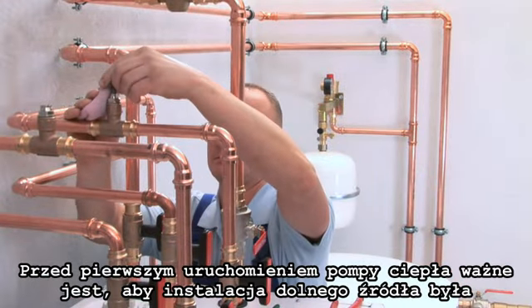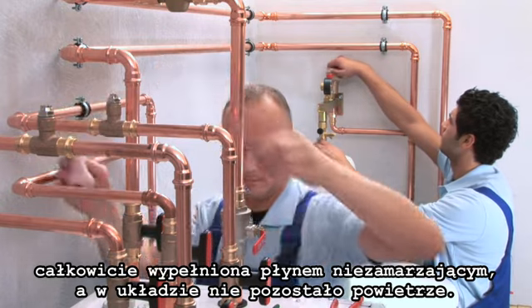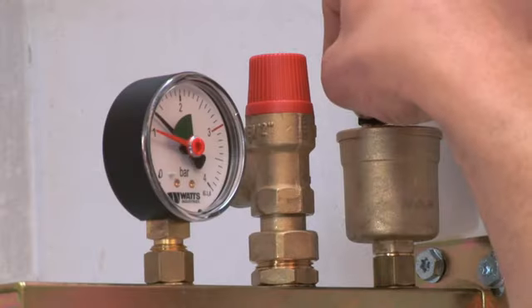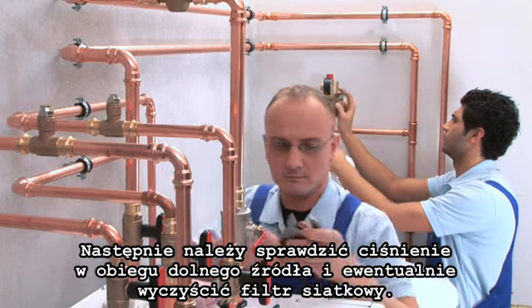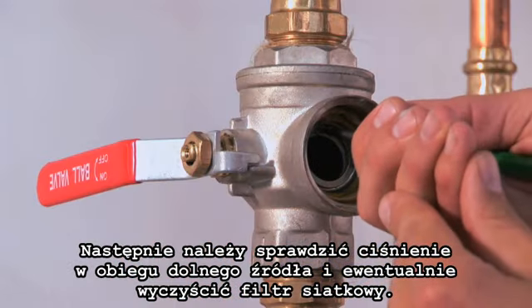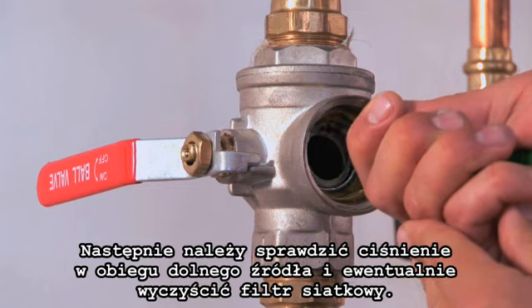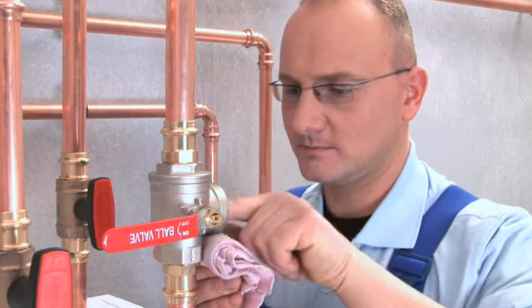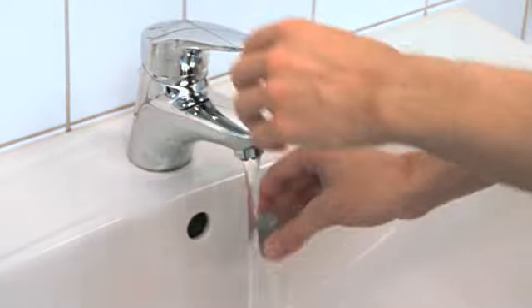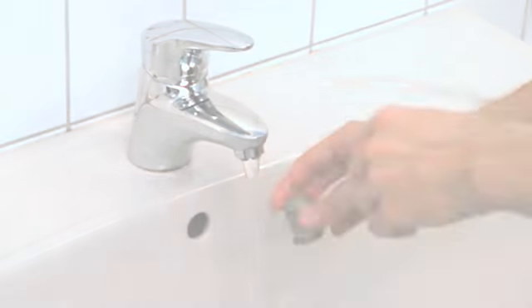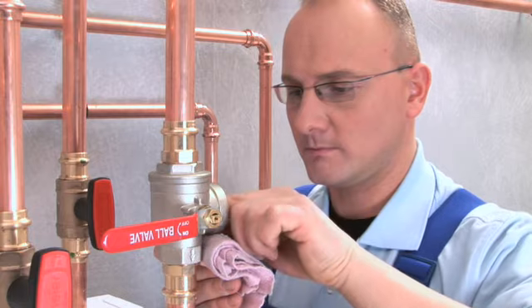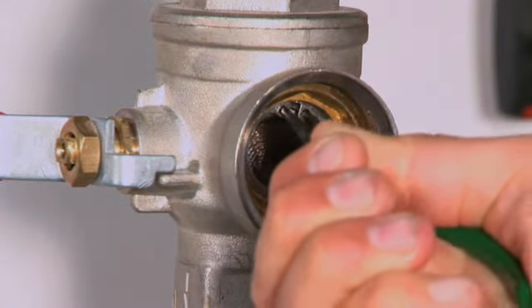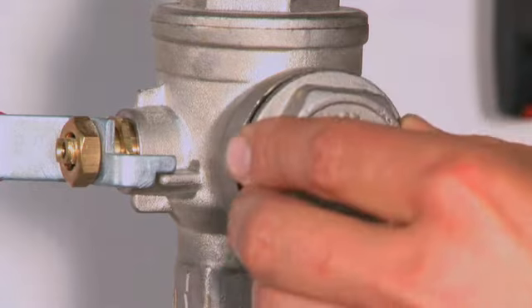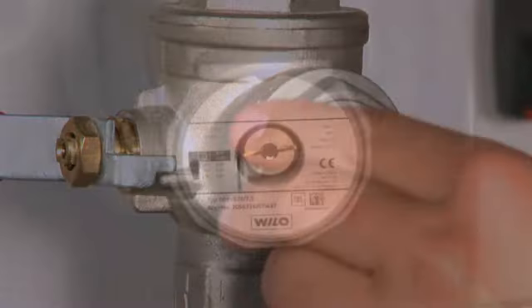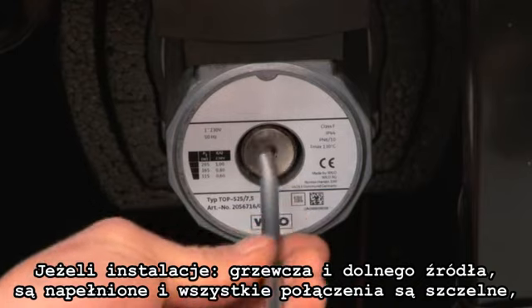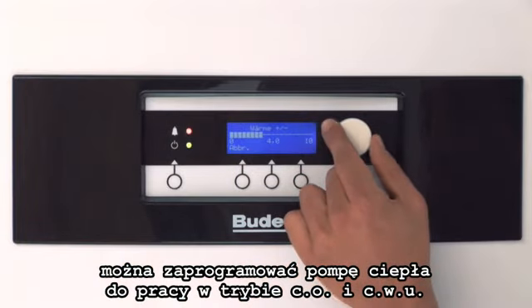It is very important that the system is completely filled and there is no residual air left. Then check the pressure in the brine circuit and clean the contamination filter if necessary. When the pump is operational and all connections are tight, you can program the system for the heating and warm water operation.